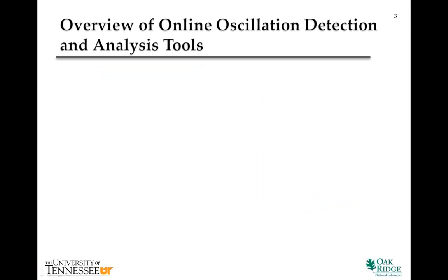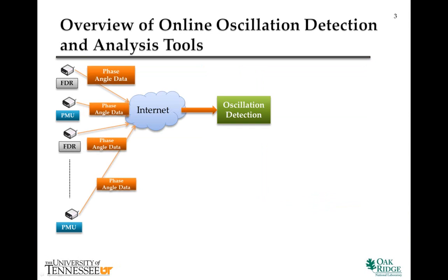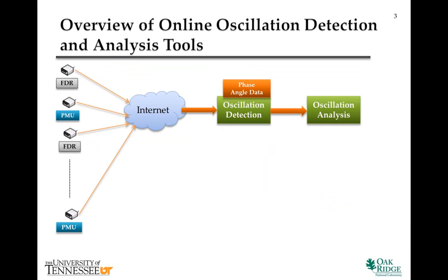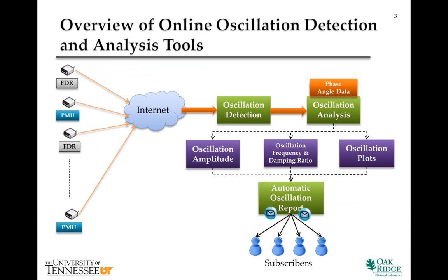The phase angle data are used for oscillation detection and analysis. The oscillation analysis module calculates amplitude, oscillation frequency, damping ratio, and generates plots. Automatic oscillation reports will be sent to subscribers through email.